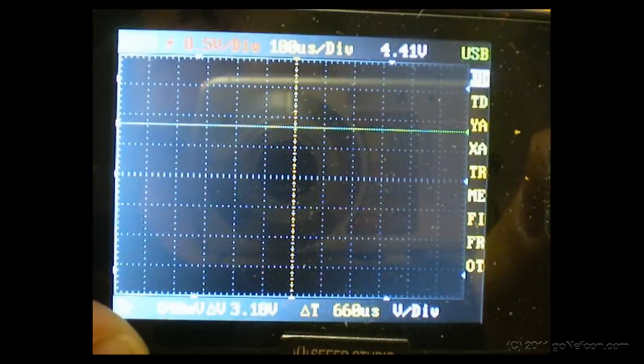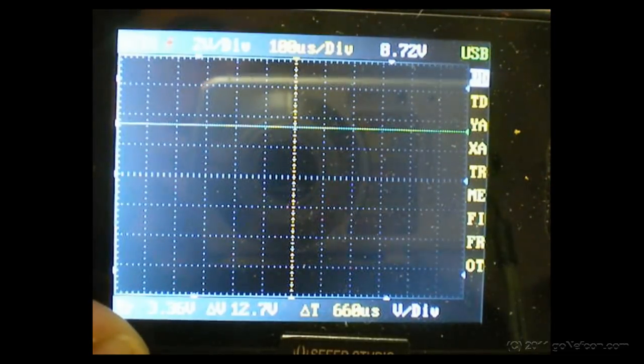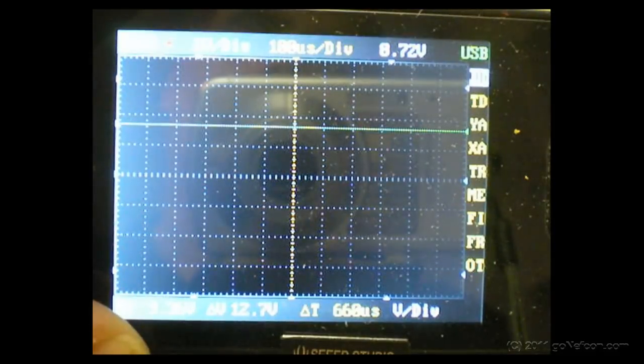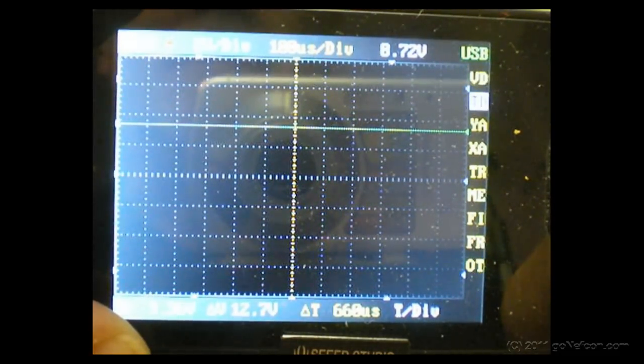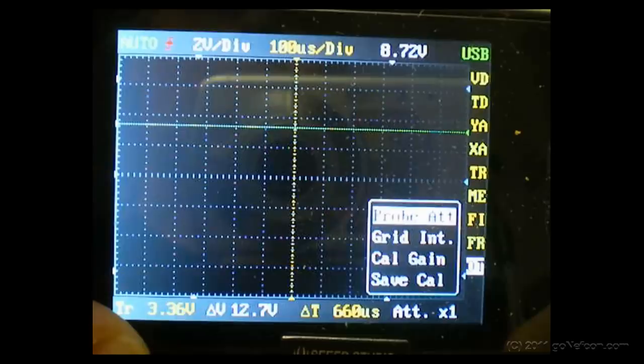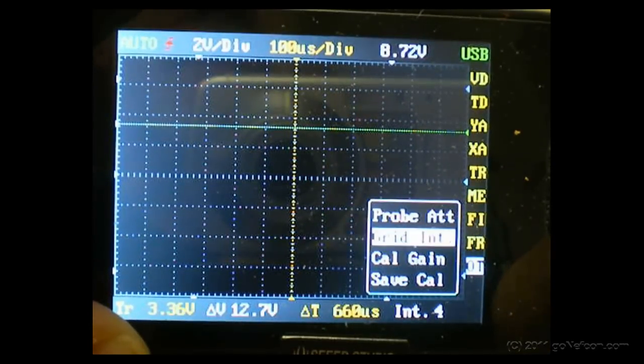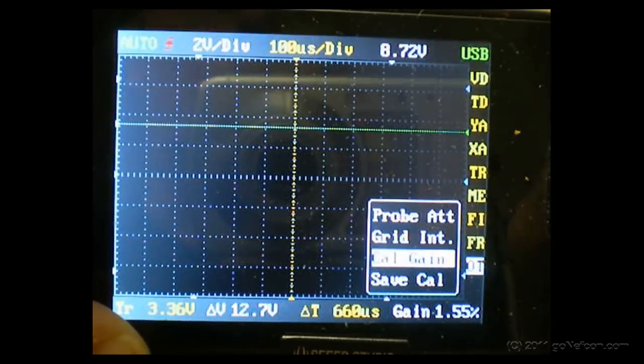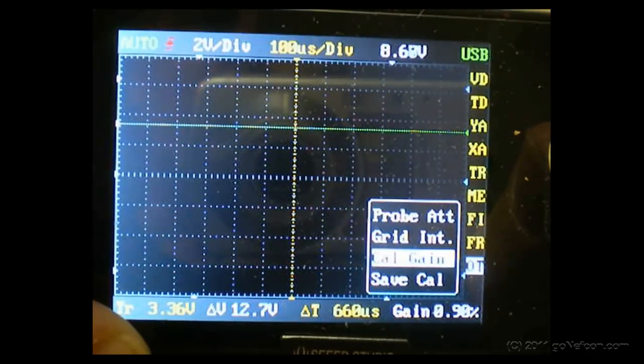Notice how the red, which says it's exceeding the range setting because it's too much voltage. Once you get 2 volts per division, then the red turns back to white right up here. So at this time, we're reading 8.72 volts, where the meter, as I showed you a moment ago, is reading 8.59.